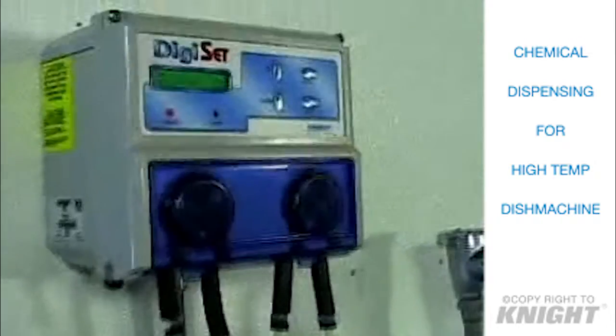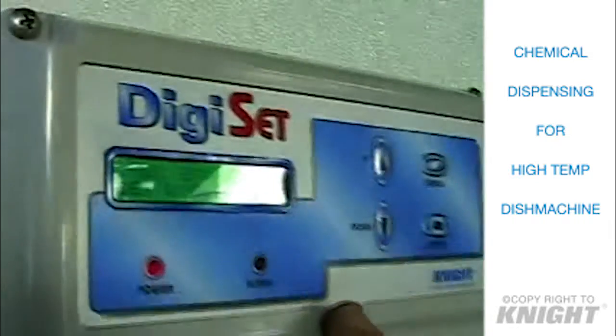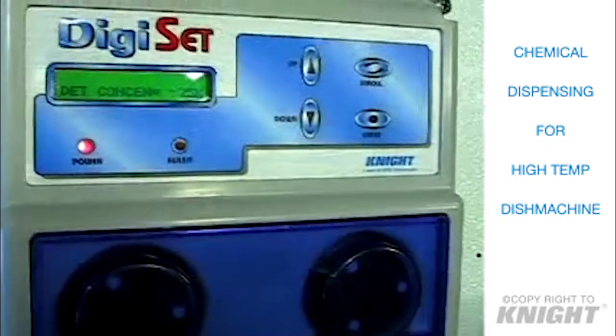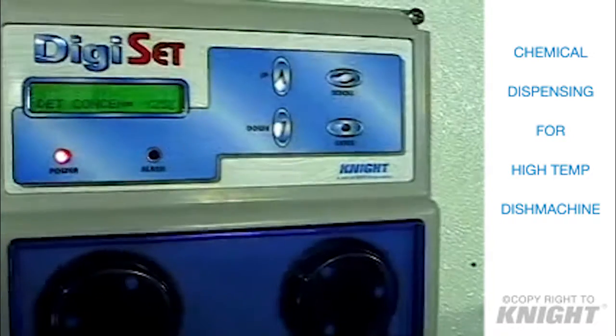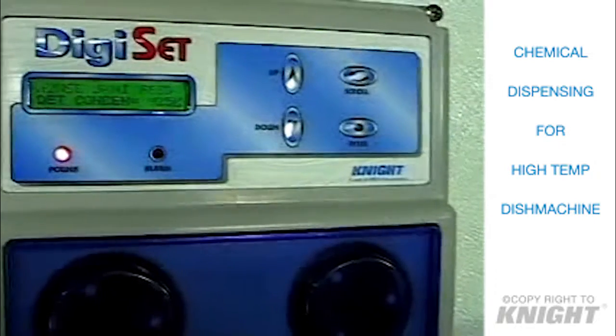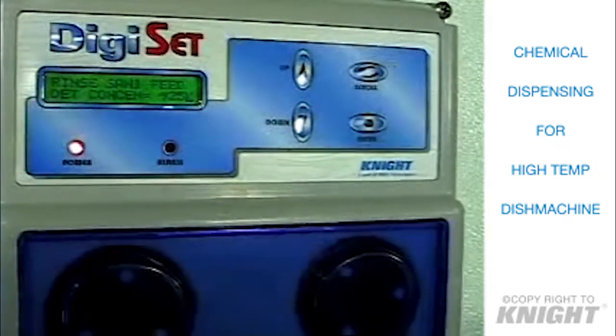So if we go up to the DigiSet and look at it, so I turn the machine on, and right now my detergent concentration is satisfied inside the machine. But if I come down here and turn on my rinse paddle, as the rack comes through here and turns this on, now my chemical pump for my rinse comes on, you can now see my rinse pump is activated. And that's from that orange and brown wire I showed you earlier. And when I let go of it, it stops.